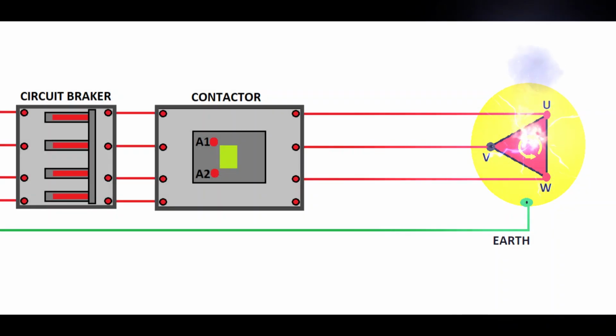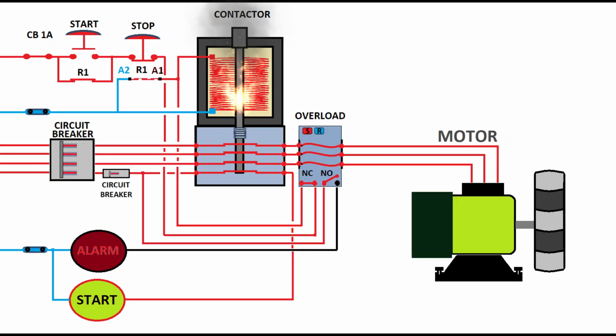The people who eliminate the overloads make the electrical circuit and the motor rely on a circuit breaker, but when the circuit breaker trips, that will be too late because your motor will already be burned. The circuit breaker is not designed to protect the motor, but it is designed to protect the supply circuit that supplies power to the motor.